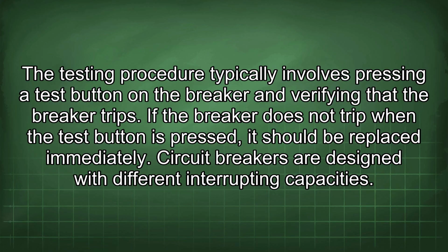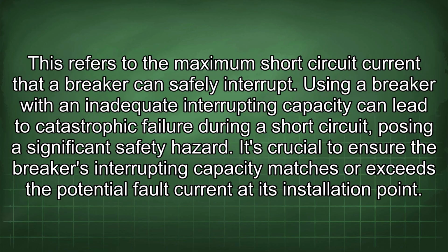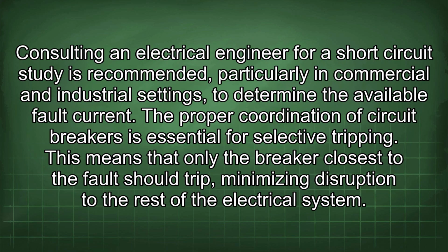Circuit breakers are designed with different interrupting capacities. This refers to the maximum short circuit current that a breaker can safely interrupt. Using a breaker with an inadequate interrupting capacity can lead to catastrophic failure during a short circuit, posing a significant safety hazard. It's crucial to ensure the breaker's interrupting capacity matches or exceeds the potential fault current at its installation point. Consulting an electrical engineer for a short circuit study is recommended, particularly in commercial and industrial settings, to determine the available fault current.